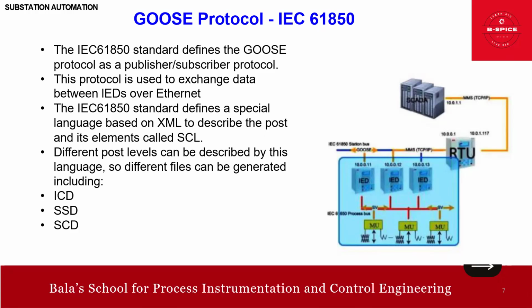Then, of course, interoperability. GOOSE messages are designed to be vendor independent, allowing devices from different manufacturers to communicate seamlessly within the substation network. Overall, friends, the GOOSE protocol plays a vital role in modern substation automation, providing fast, reliable, and efficient communication for protection and control systems. So that is about GOOSE, friends.